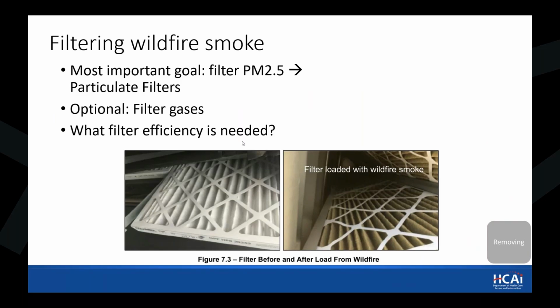at least a MERV 13 minimum filter for most facilities, which is really not that high of a bar, given a variety of other codes and standards that typical healthcare projects go through. MERV 13 is usually where you end up landing for most of your basic filtration within the air handling systems, and so it's not as though you need to substantially impact the performance of your HVAC system in order to achieve that. So I think it would be highly recommended.